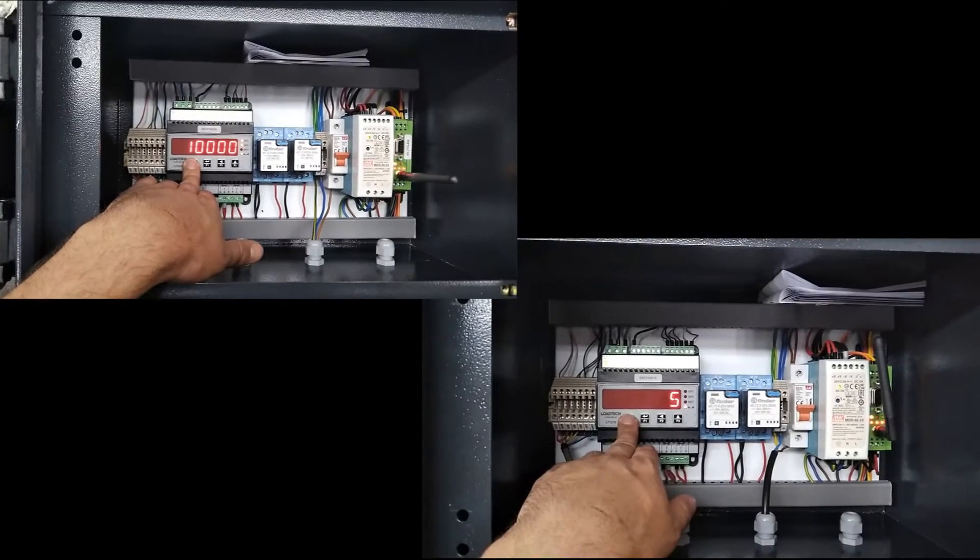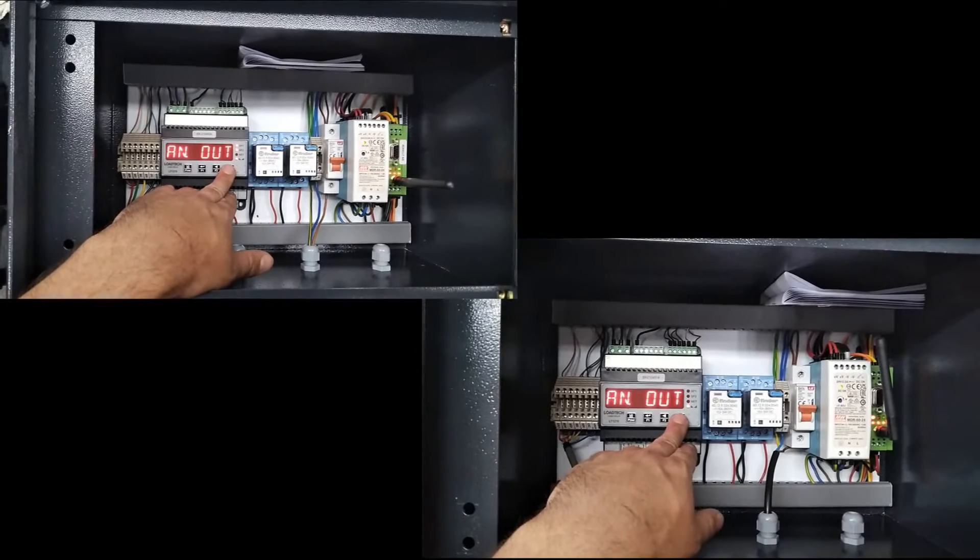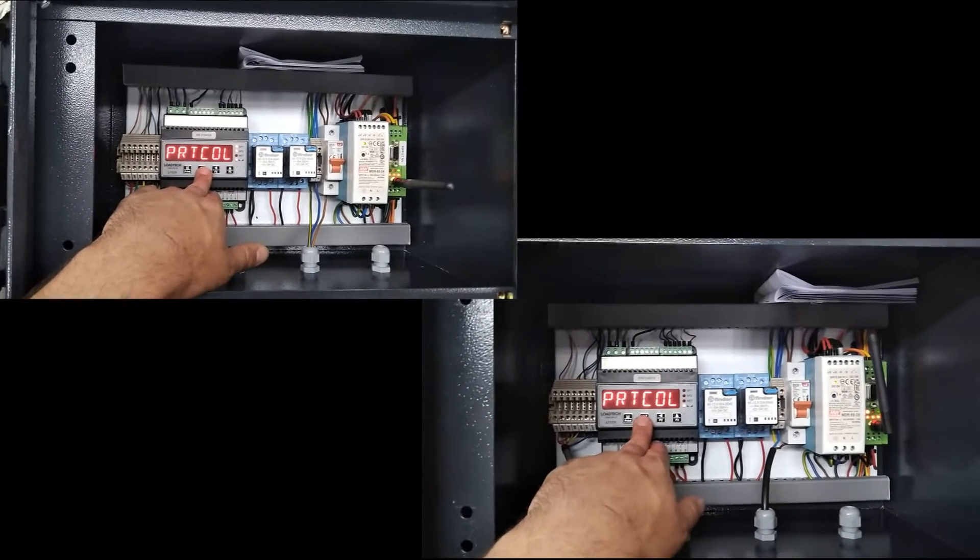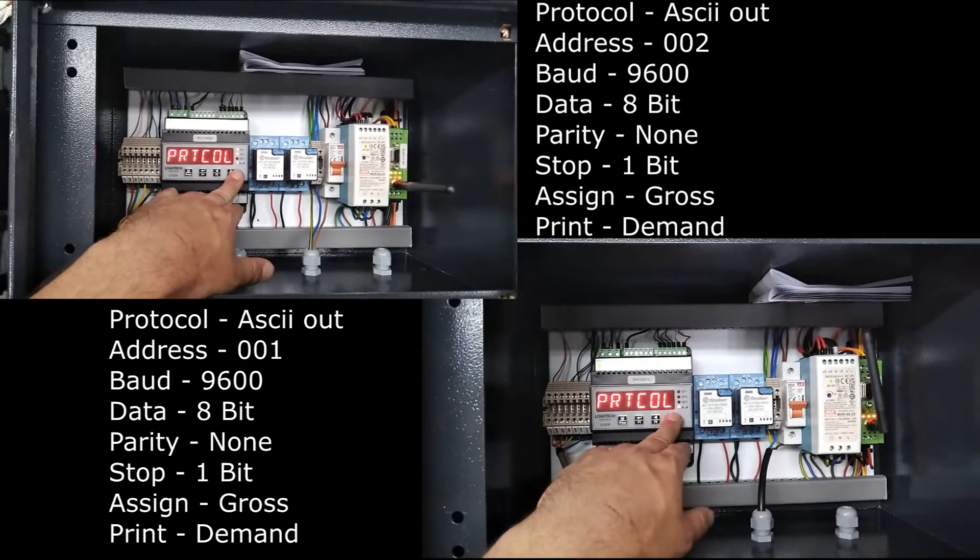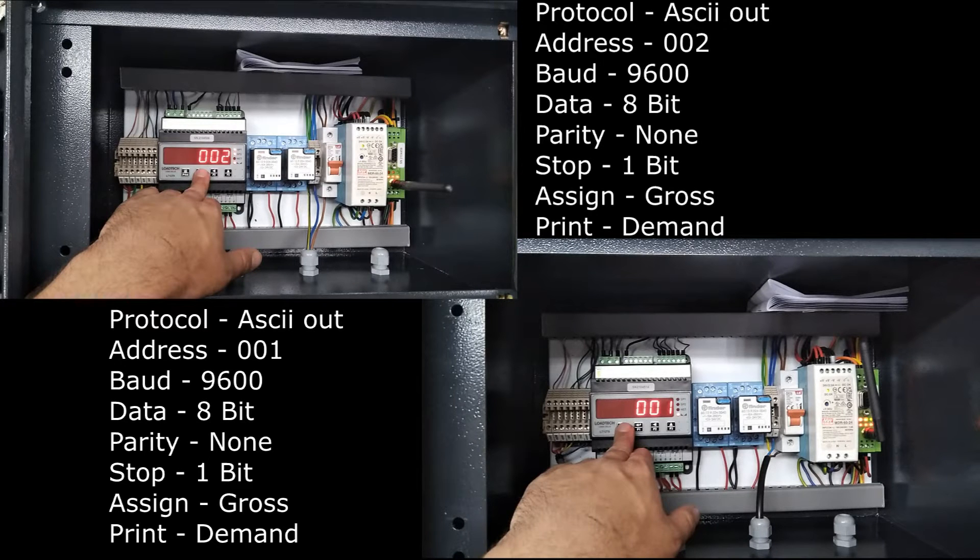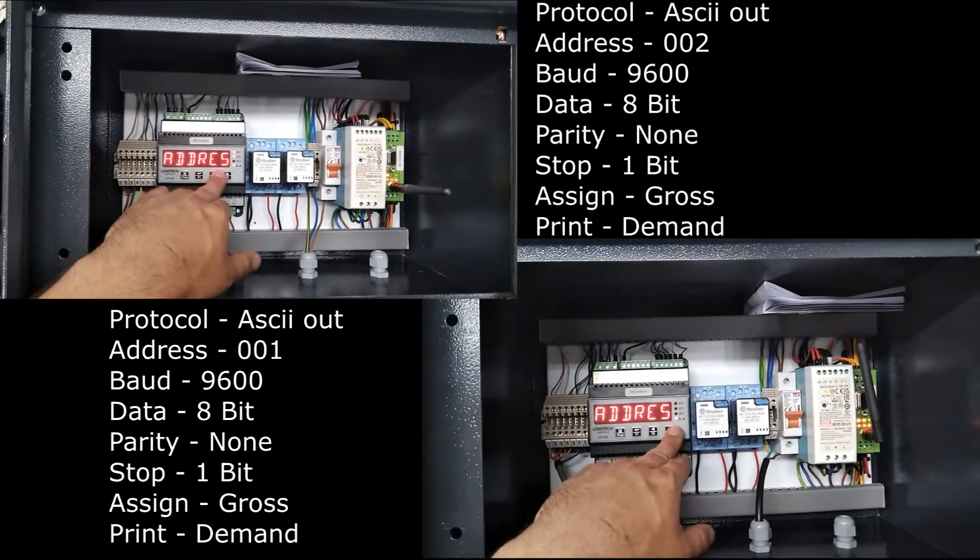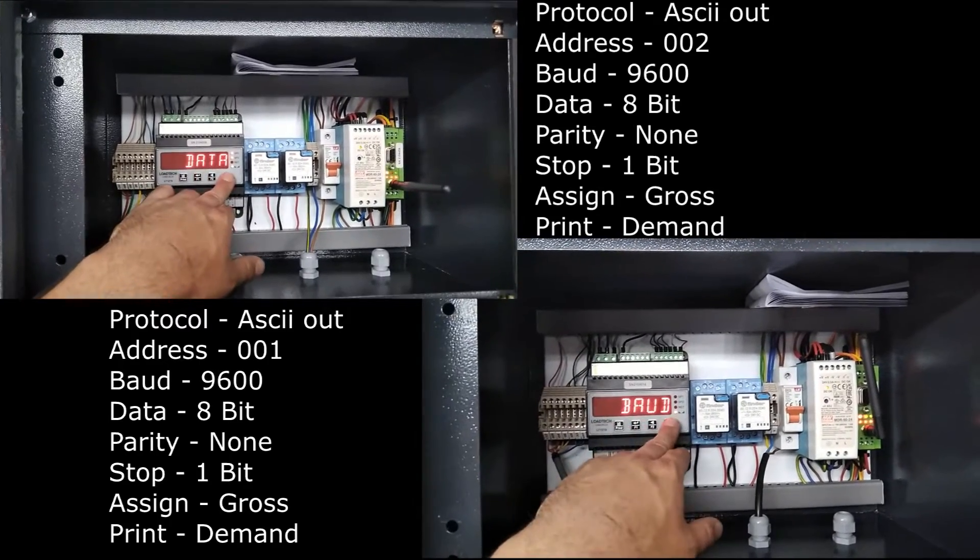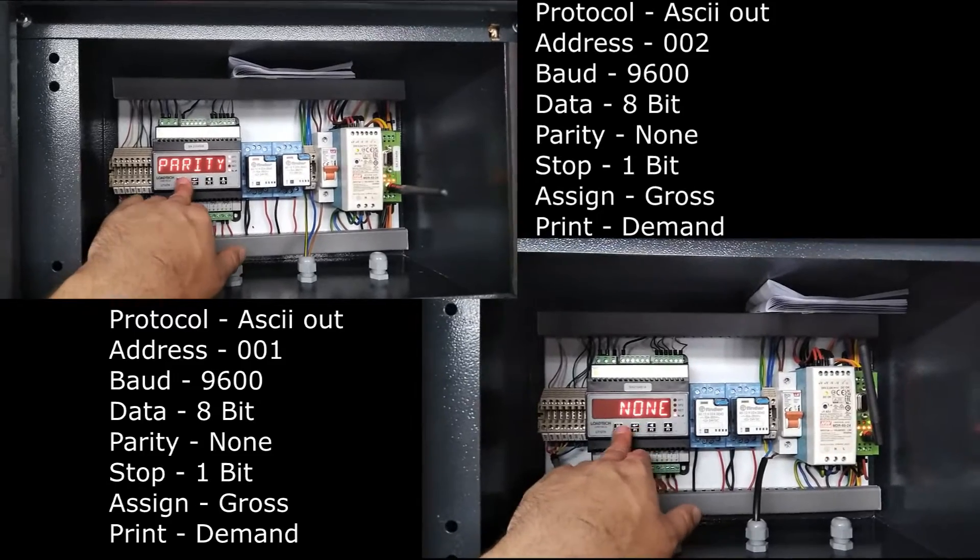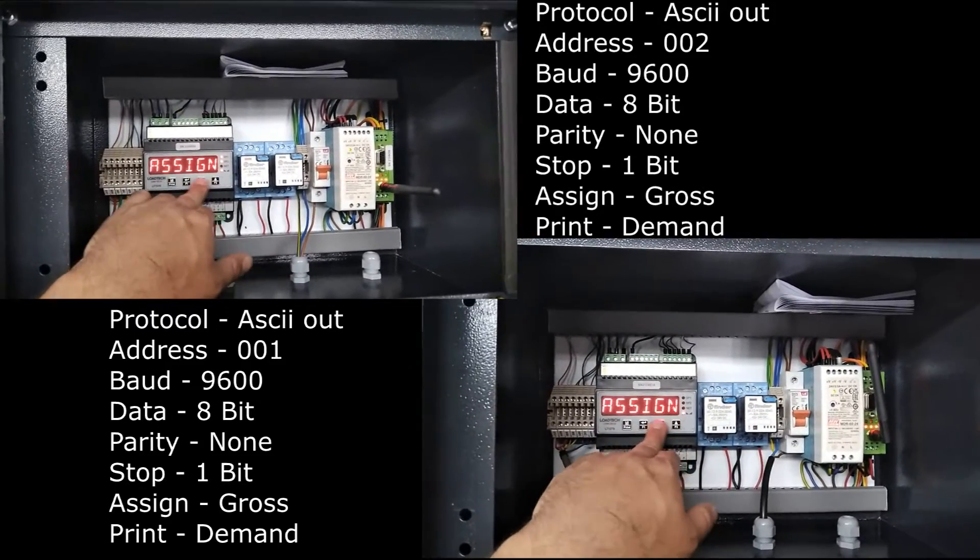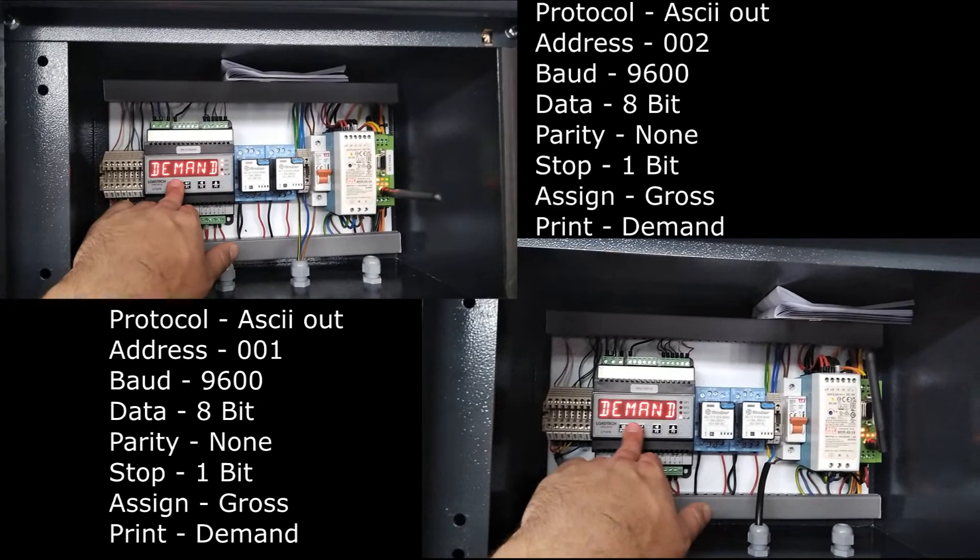First off, starting on the 1270 or 1240, hold your menu button, navigate to RS-485 and the settings will be on screen as follows. Protocol will be ASCII out. The address will be 001 and 002 respectively. The baud rate will be 9600. The data will be 8-bit. The parity, none. Stop will be 1-bit. Assign will be gross and print will be on demand.